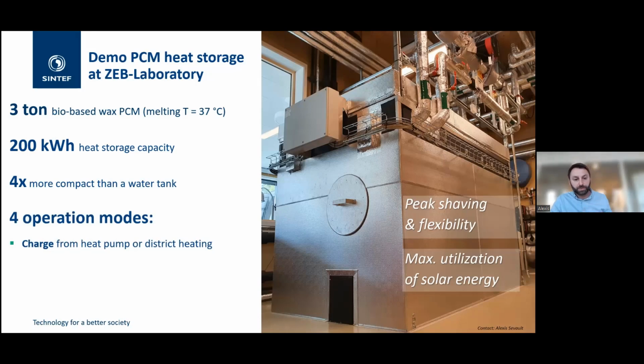And we can also charge from the district heating. Here on this building, we are connected to the return loop of the district heating. That means we can get the heat at about 40 to 47 degrees. It's the district heating network from the campus here. And we can discharge in 2 different ways to the heat pump. Let's say it's very cold outside and you need more heat than your heating system can deliver.